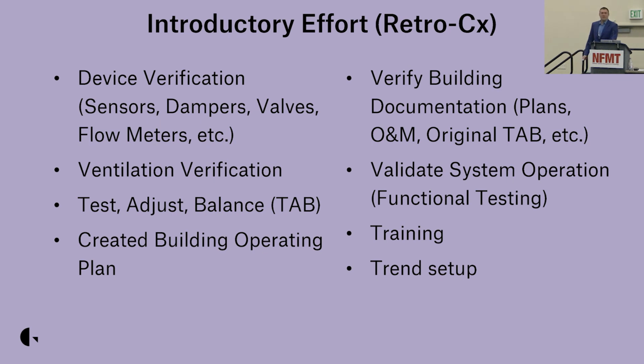Verifying the ventilation - you want to have your positively pressurized building. If you don't have that, you are going to have moisture issues, you're going to have all kinds of issues. A lot of times you'll go back in and do test and balance effort just to make sure that everything's performing the way you think that it is.